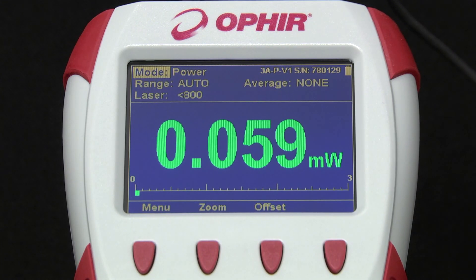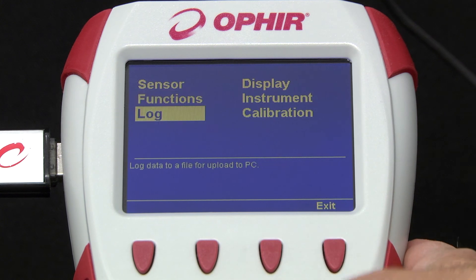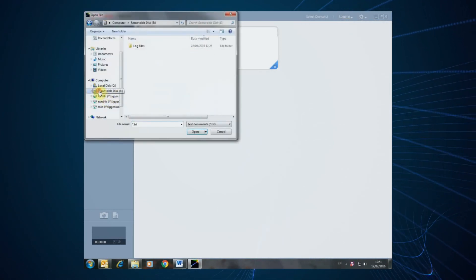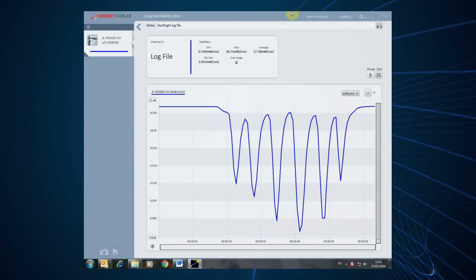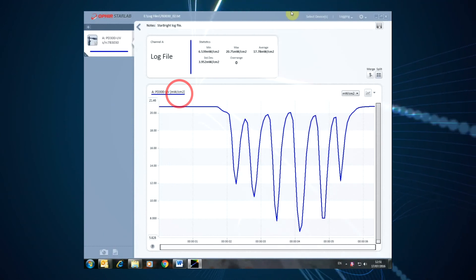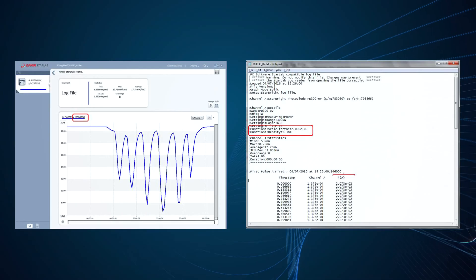To log data onboard Starbright, insert a USB flash disk in the slot and go to the Log function in the menu. You can later access the file storage and upload the stored data from the flash disk to a PC running the Ophir Starlab software application. Note that when using any of Starbright's special functions — such as Density, Normalize, or any combined functions — Starbright logs the actual function results. This is a feature unique to Starbright.